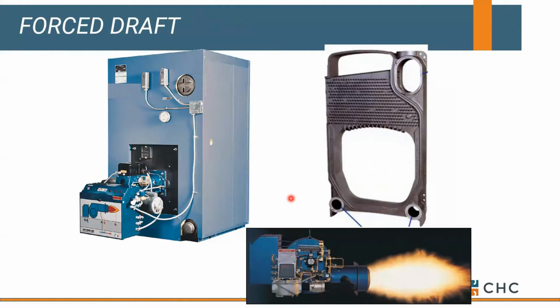You can also look at what we call forced draft. They're still a fan assist, but these are like power burners. They almost look like a jet engine, if you will, burning natural gas, propane, or number 2 fuel oil like diesel. And all they're doing is sending hot flue gas down the center of the boiler. And this section is actually full of water. It's hollow in here, so you have water that circulates around and is picking up that heat. It all collects, and either you send steam out to the system or hot water, depending on how you have it configured, okay?